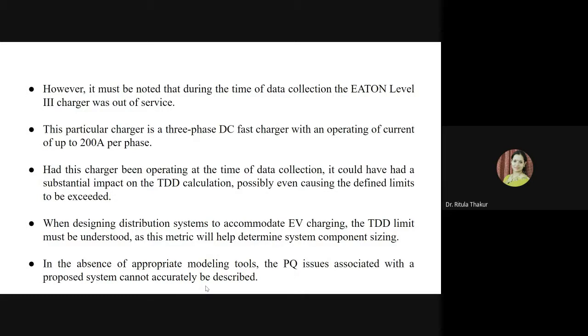So if this was operating at the time of data collection, it could have had a substantial impact on the TDD calculation, possibly even causing the defined limits to be exceeded. So now they are becoming happy that we are within limits of 8%, but one of the major factors could be that at that time the level 3 charger was out of service. So that could also be one of the reasons why they got the TDD within the limits.